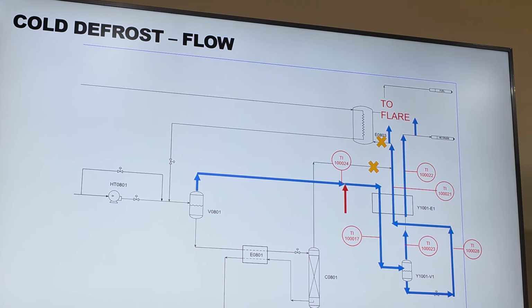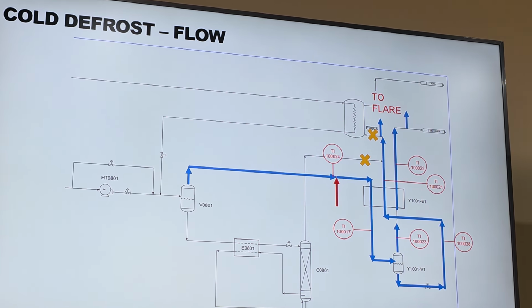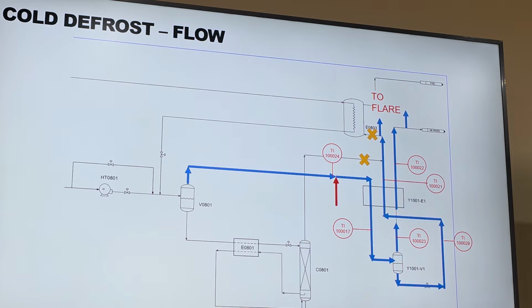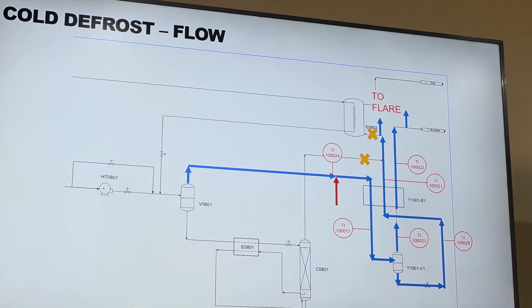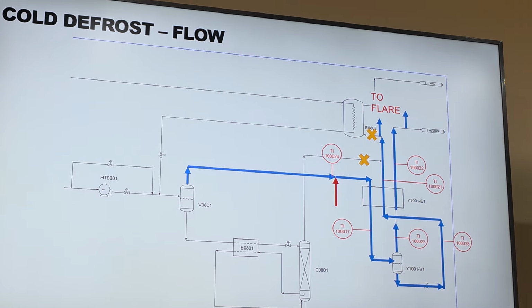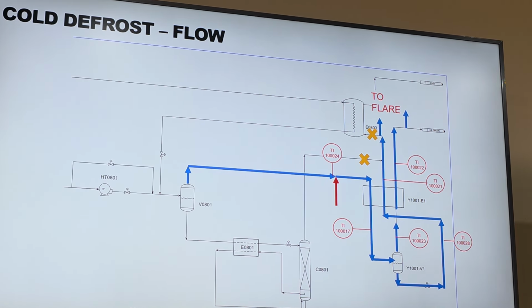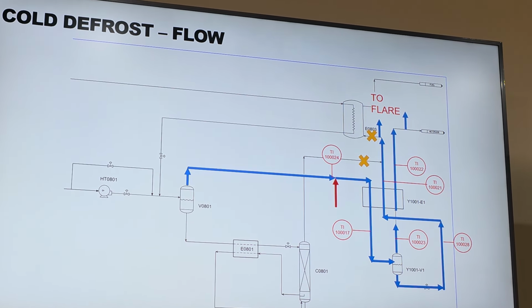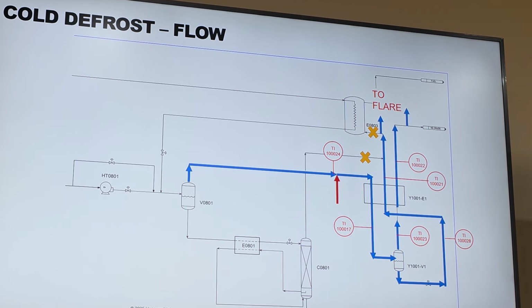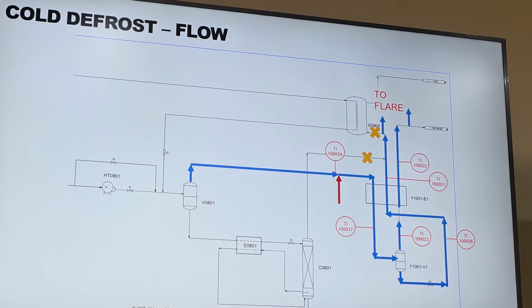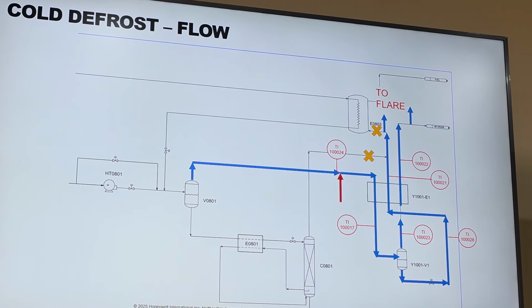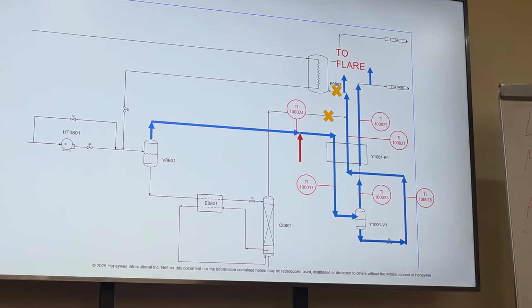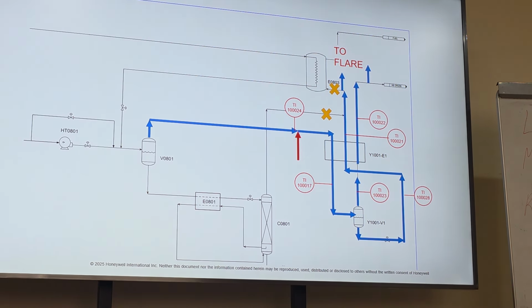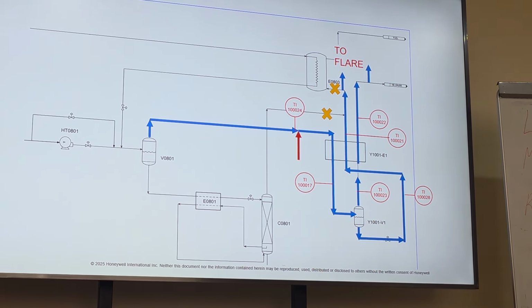And how cold can you make that gas? It's minus 35, same minus 35. From the other train we have this interconnection as well. Let's say this train is down and you really need to warm it up. You have cold gas available, so you can bring it up to the unit 8 and put it into the unit, because that cold gas is coming from the pre-cooling. Pre-cooled gas, still minus 35. Okay, the second option is really just a small put around this defrost gas and that is all. Okay.